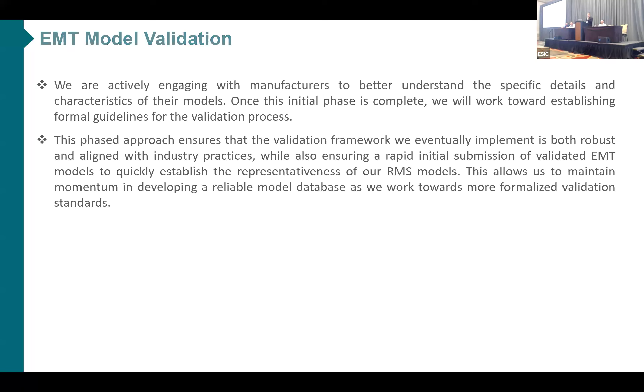As I said, for the EMT validation we don't yet have formal guidelines, but for the EMT versus RMS validation, the validation of the RMS model, there is a very specific guide with requirements regarding simulation time window, sampling rate, format, and grid structure. There's a list of variables to collect and very comprehensive test scenarios with voltage and power steps, frequency excursions, shunt switching, faults, oscillation events, LVRT, HVRT tests, and so on. So for this specific validation of the RMS models, there is a very detailed guide.